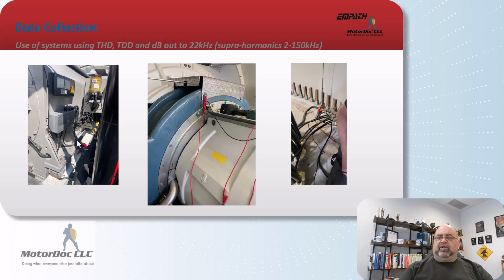So this is an example from the first company of where current data was taken. So on the generator itself, this is voltage and current on a brush on the main bearing, and then this is the size of the ground lead for basically three double-aught. I'm sorry, is it 1-aught or aught cables going up? Each cable's about yay round. And there's 3 cables on this particular design per phase, so it can carry about 1,500 amps. That is not going to carry fault current from up tower. So that's strictly lightning protection. And then they ground all the way up the ladder so you don't get shocked as you go up to 240 to 350 feet.